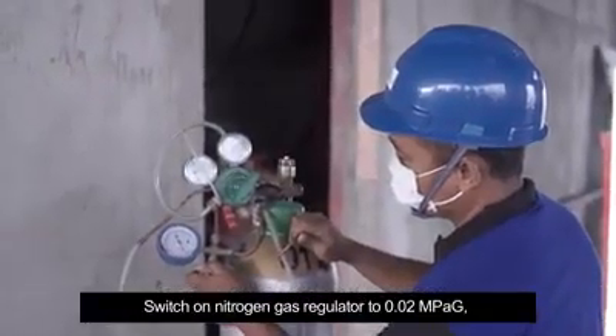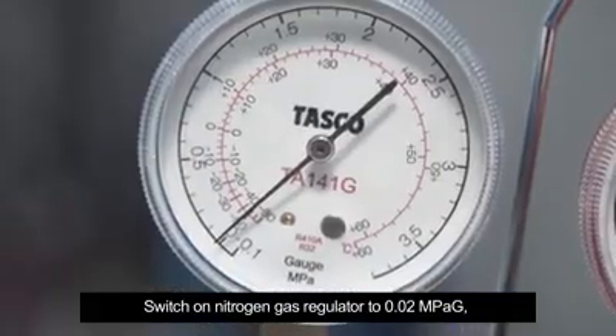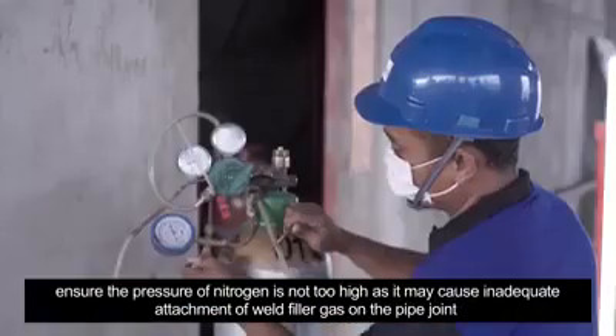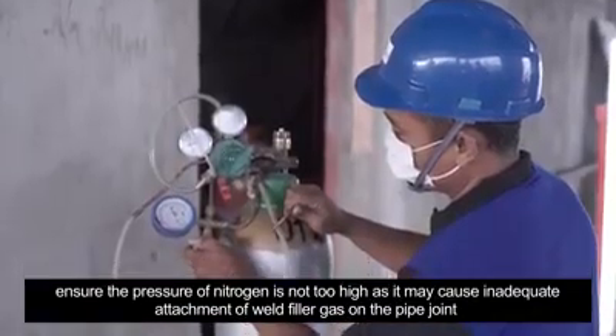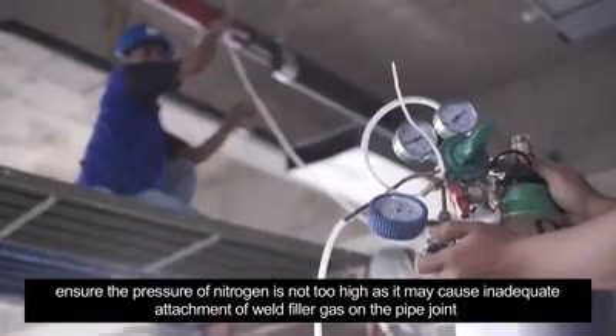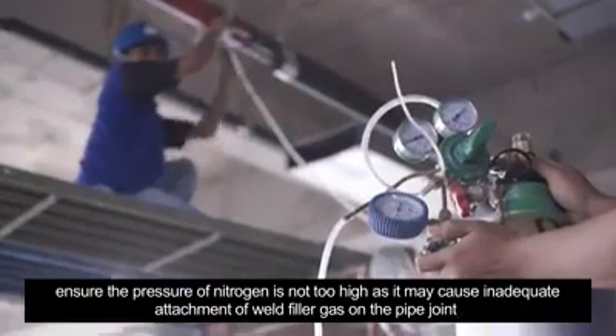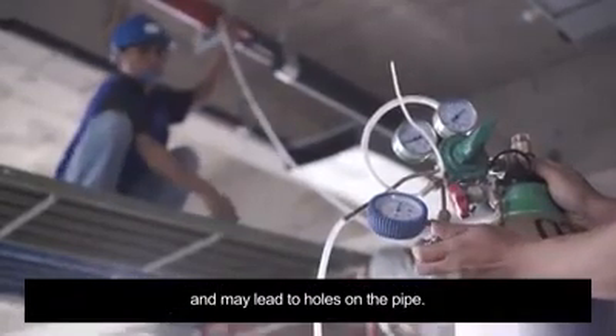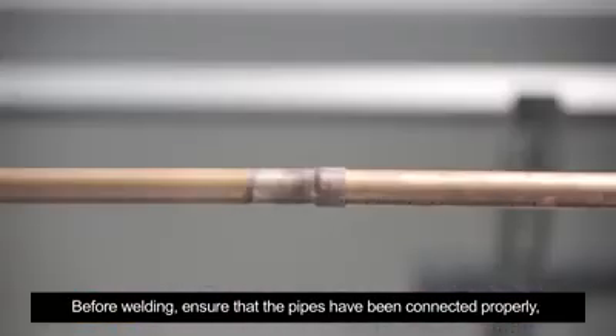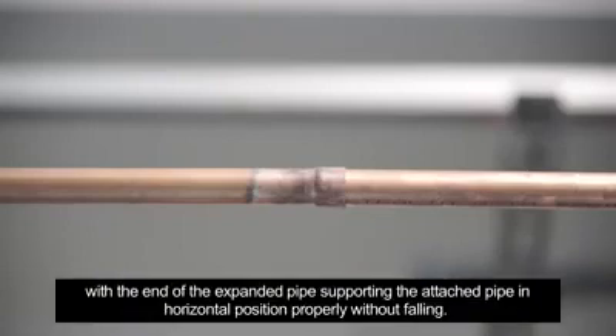Switch on nitrogen gas regulator to 0.02 megapascal. Ensure the pressure of nitrogen is not too high, as it may cause inadequate attachment of weld filler gas on the pipe joint and may lead to holes on the pipe. Before welding, ensure that the pipes have been connected properly, with the end of the expanded pipe supporting the attached pipe in horizontal position properly without falling.